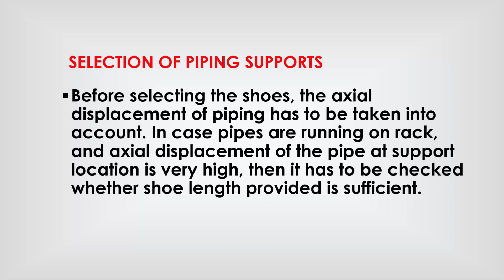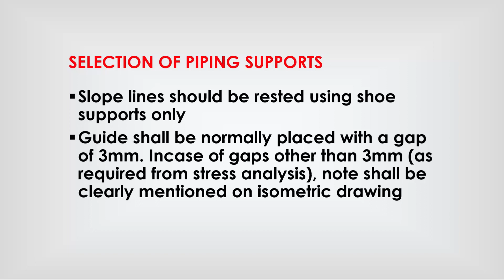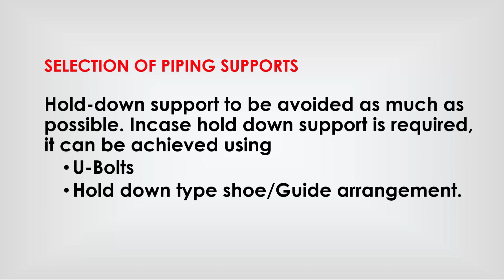Guides shall normally be placed with a gap of 3 mm. In case of gaps other than 3 mm, as required from stress analysis, notes shall be clearly mentioned on the isometric drawing. Hold-down support to be avoided as much as possible. In case hold-down support is required, it can be achieved using U-bolts or hold-down type shoe guide arrangement.